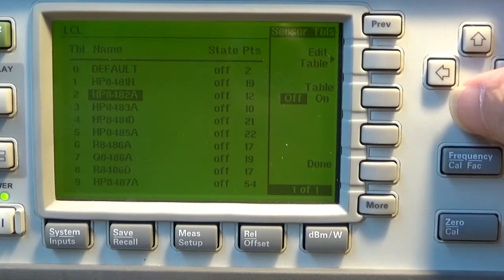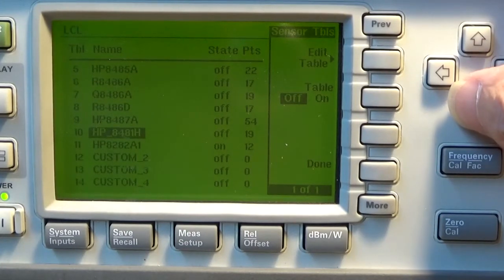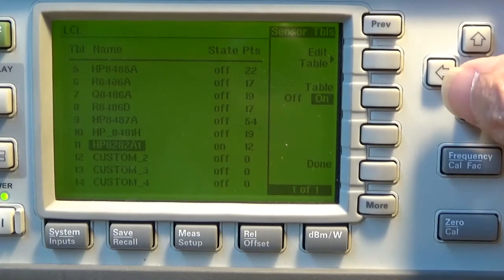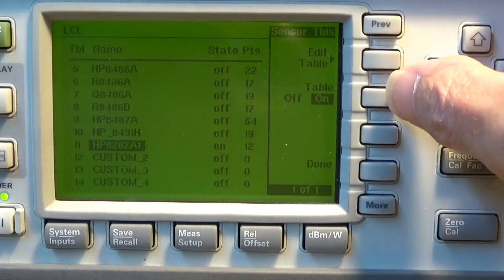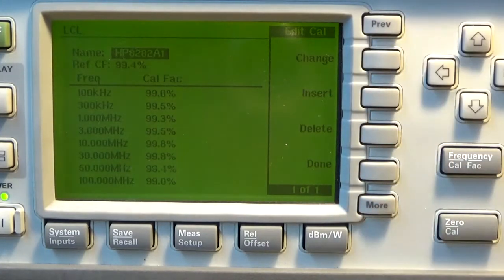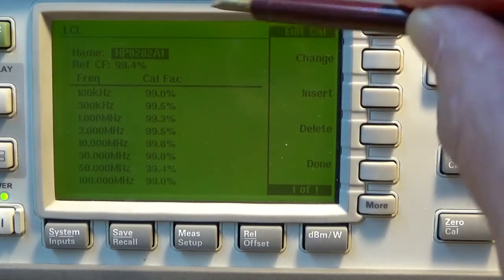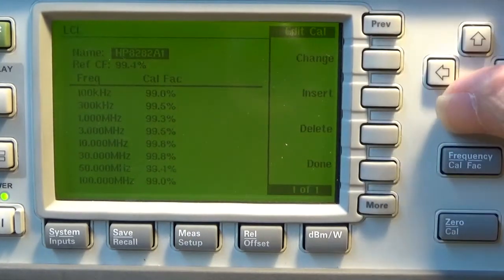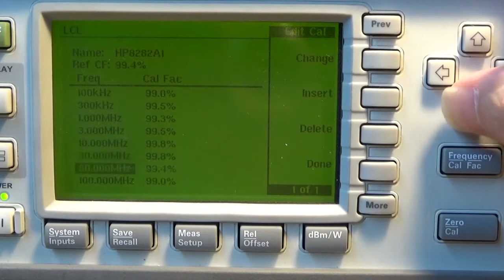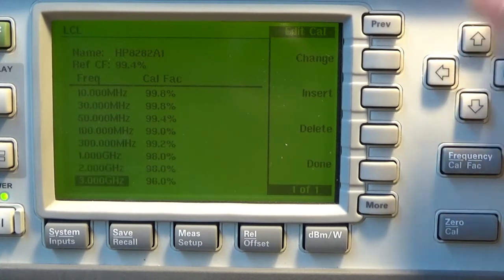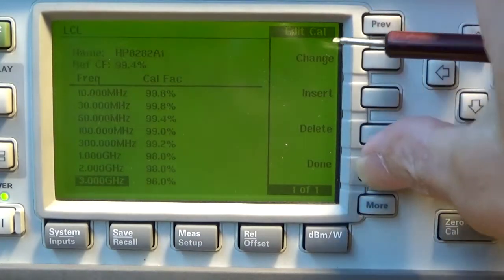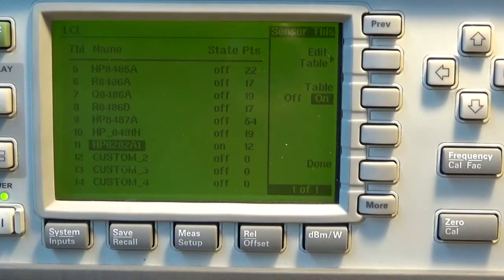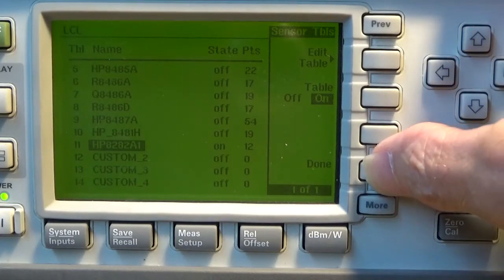That's not the one I will use, because that's, as I said, just the average. But you can put in your own. So I've gone down to custom, which is number 11 on there, and if I select that, or edit it if you like, that's where I've set in all my values, starting at 100 kilohertz and going all the way down, right to 3 gigahertz, basically at 96%. So I've done with that, and that's the one I've got turned on. So all the measurements it takes will be with reference to that table. So get out of that.